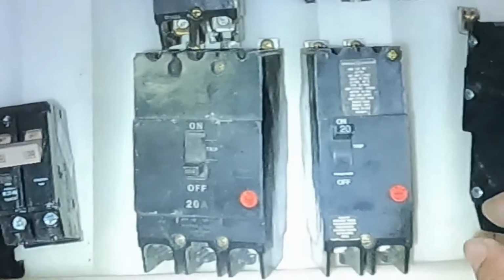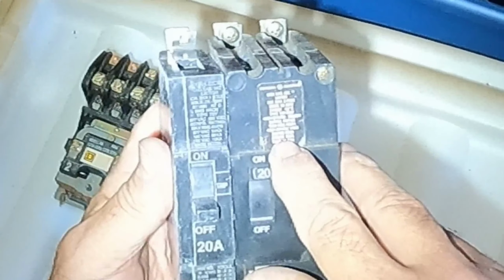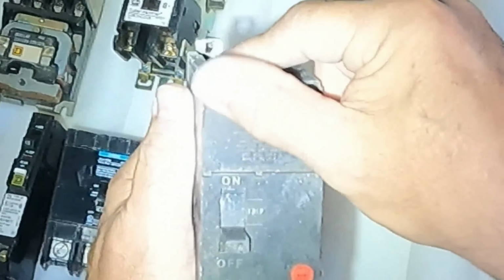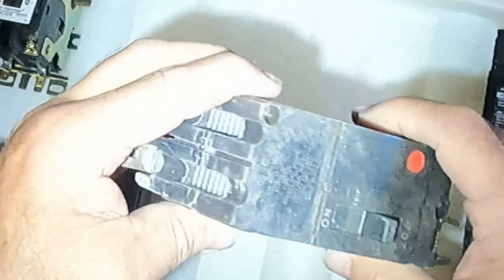And what was the other guy? It was rated at 250 volt. This one's rated at 125. I don't know if it's 125 per pole. This is a really oldie. This is rated 250 volt, 10 KIC. I guess it's the same breaker, just a little dirtier. And it doesn't say must be used in a listed enclosure. So you can actually connect this outside and use this as your disconnect for your battery bank or your solar input array, as long as you don't exceed.